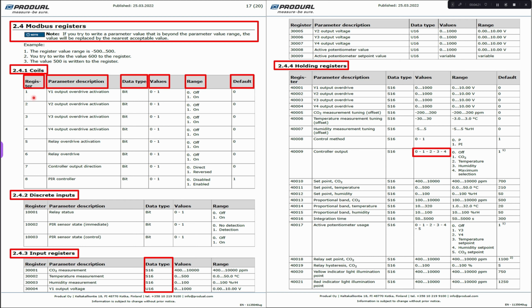Registers start from 1, and in this case, it's shown in data address mode. Possible range 0 to 65535. Depending on the model, register number listing and manufacturer, the presenting mode could vary. Some coil registers could be presented as 0, 1, 10,000 or 10,001, so there can be an offset of 1. Very often the real value is 1 under the shown value, like in this case also.